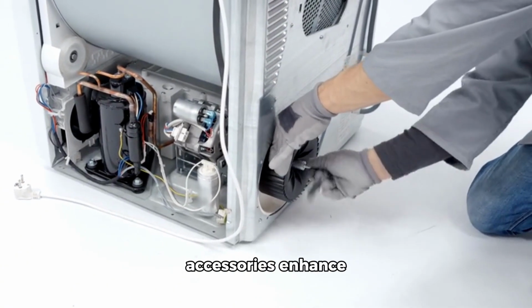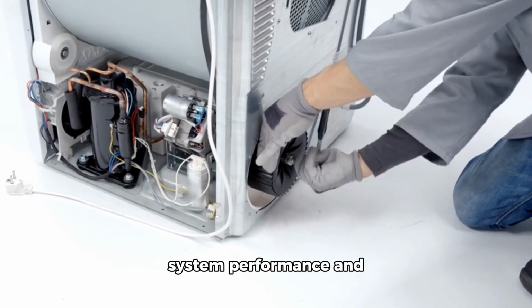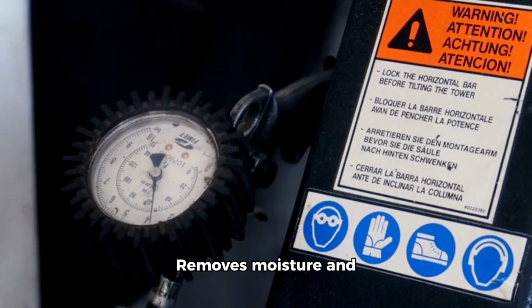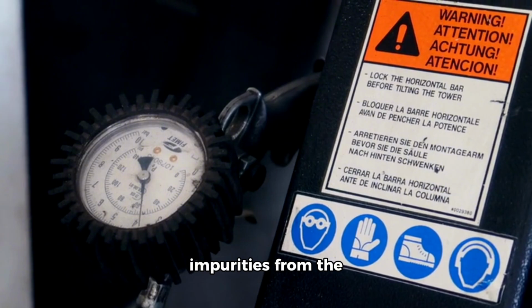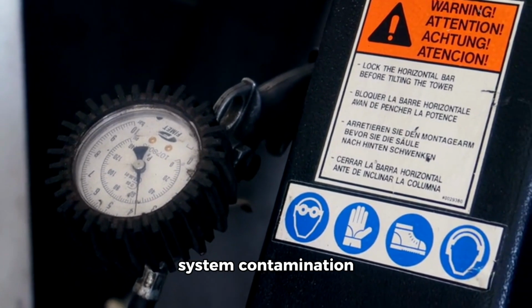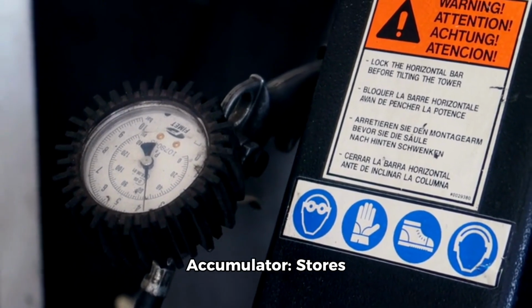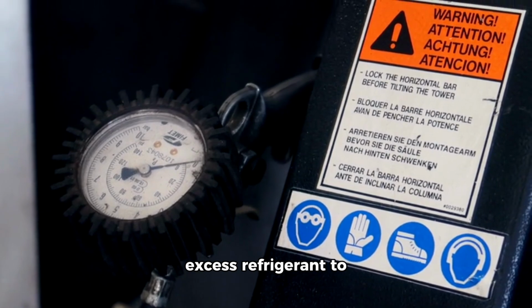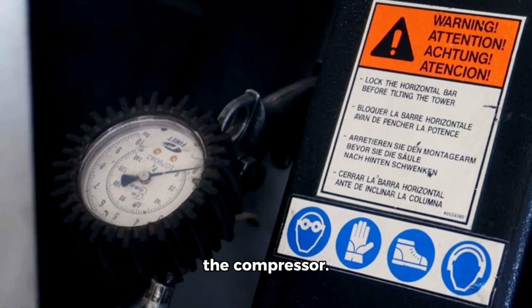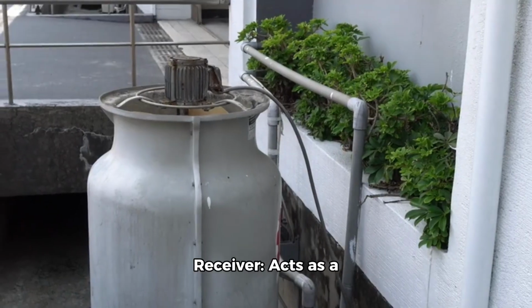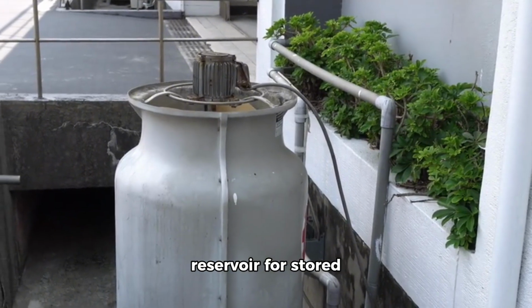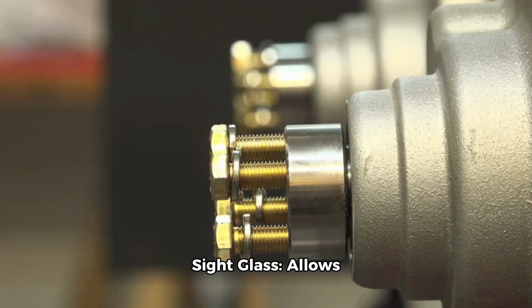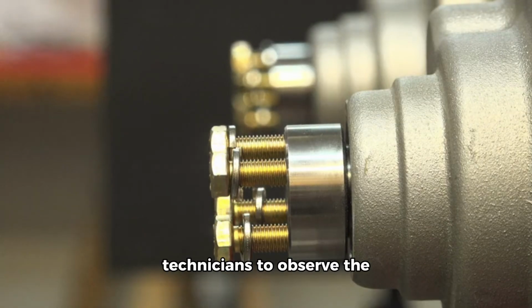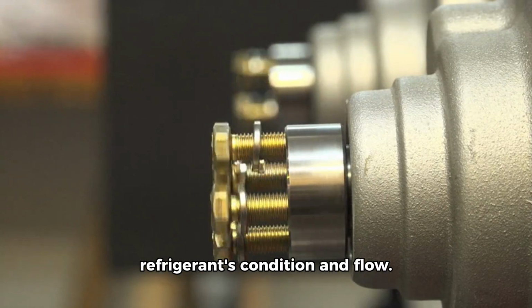Additional accessories enhance system performance and include the filter dryer, which removes moisture and impurities from the refrigerant to prevent system contamination. Accumulator stores excess refrigerant to prevent overflow into the compressor. Receiver acts as a reservoir for stored refrigerant in the liquid stage. Sight glass allows technicians to observe the refrigerant's condition and flow.